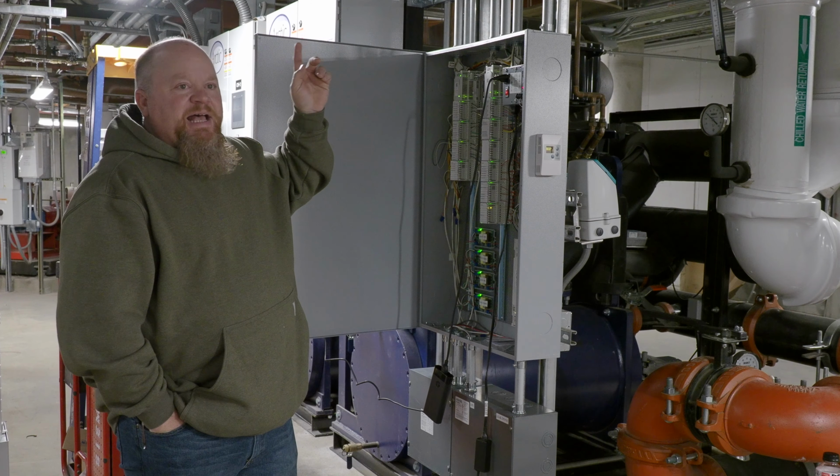So were you planning to use pumps then? We ran them. Yeah, we had the system up and running. Brad from Tri-County was able to start up and do the full startup on each individual chiller. We ran into some issues with the metal, the rust and stuff in the cooling towers, that plugged up all the cooling towers. We had to stop running it.